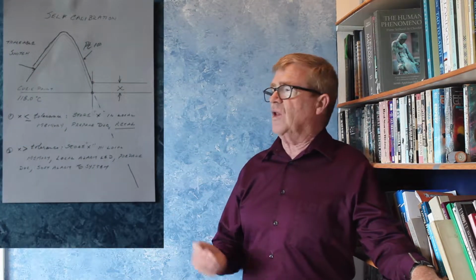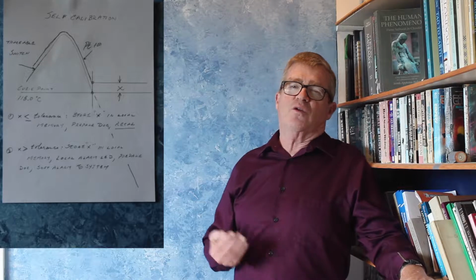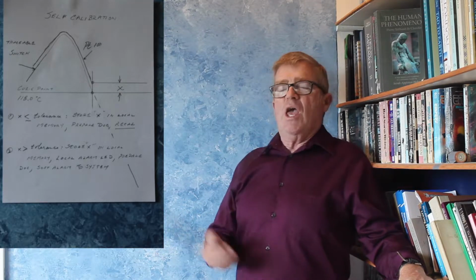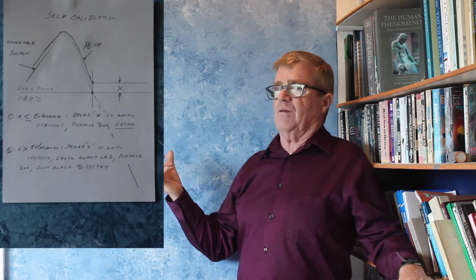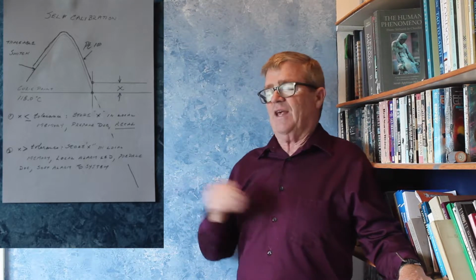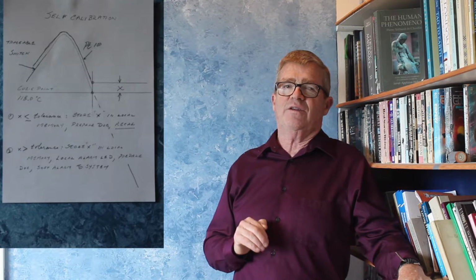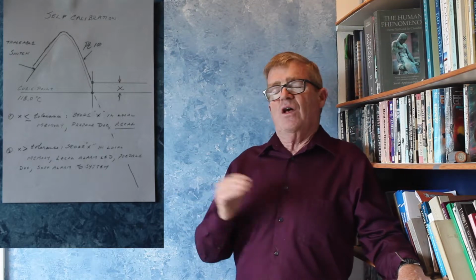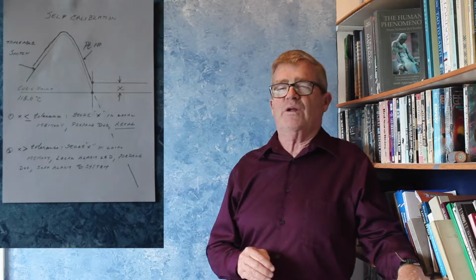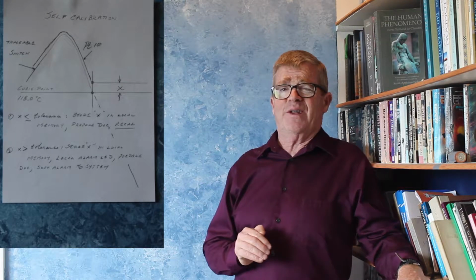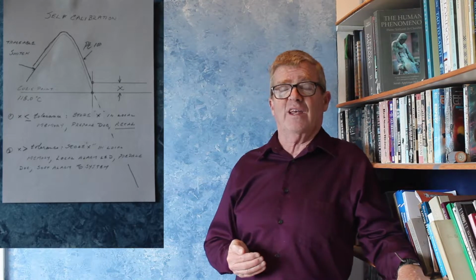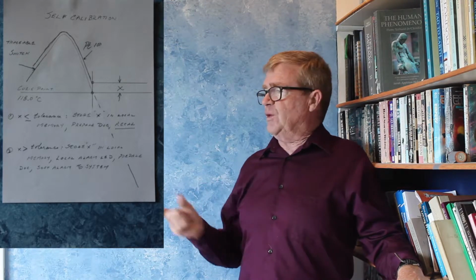Now what does Endress and Hauser mean by self-calibration? Well, let's take, for example, if we were to install this in an autoclave. Here we have the autoclave cooling down from some temperature peak. It passes through the device critical temperature, which in this case happens to be exactly 118 degrees. When that happens, the software queries the PT100 and says, we just passed through 118 degrees. What temperature do you think it is? It takes any difference between those 2 readings and calls it calibration data.